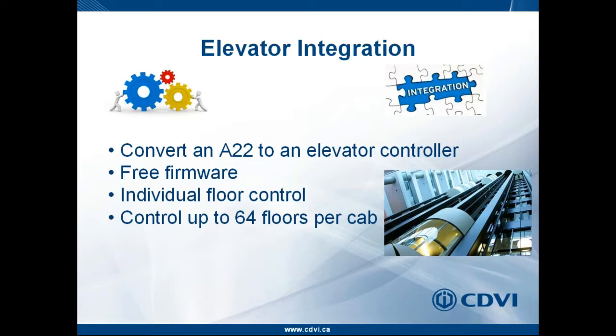The Centaur Elevator Controller, part number CA480A, is a relay board with 16 relays, controlling 16 floors per unit. The A22 with elevator firmware communicates with this relay board. To control up to 64 floors in a single cab, four CA480A elevator controllers are connected to one A22 EC, giving 64 relay outputs total.